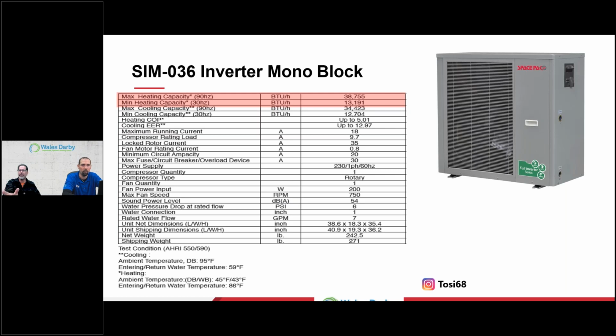So max heating capacity, here's a 3 ton: BTUs an hour is 38,755. And again, that's 120 degree water. That's a good chunk, if not most, of people's homes. We don't realize or trust the numbers. It sounds too small, right? So we want to go bigger, bigger, bigger. Just be aware until you do one or understand it for your own home.